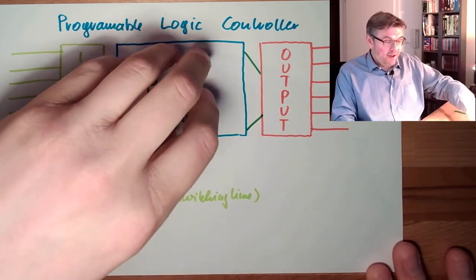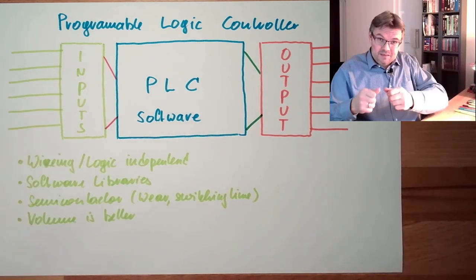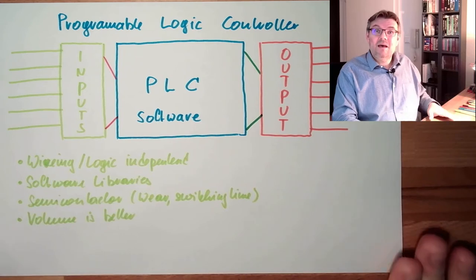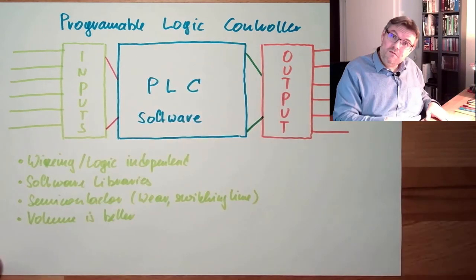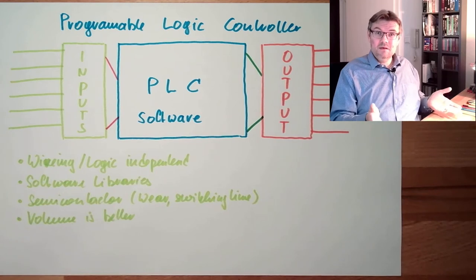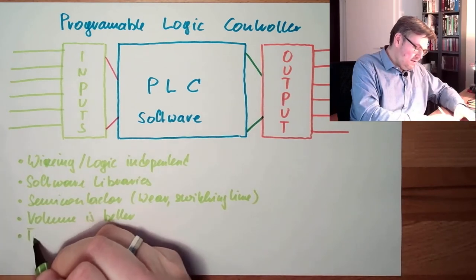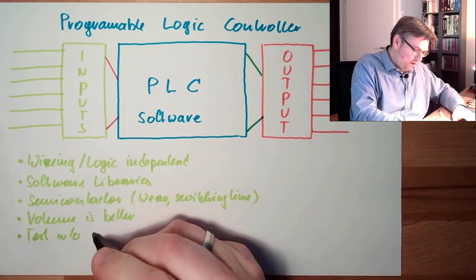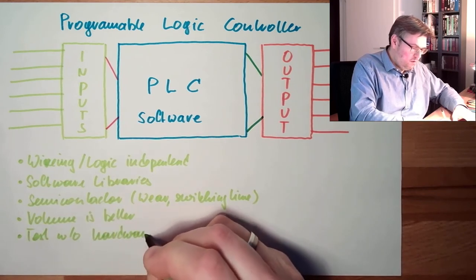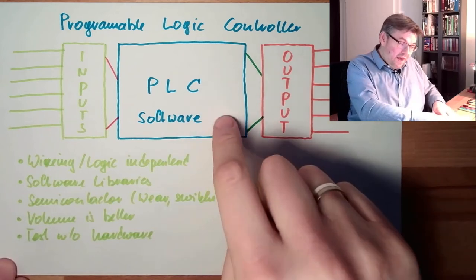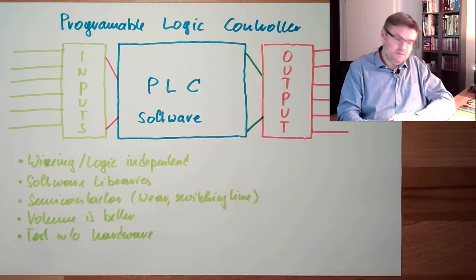I can write the software even before the real thing exists. I can write the software, check the software, make already tests with input and output, simulate different scenarios at my desk. I do not need the cabinet, I do not need the full structure of the control system, I just need the PLC, and I can already test. Test without hardware. Some programmable logic controllers, they even allow to test without an actual PLC. There are soft PLCs running a simulation on your PC available.